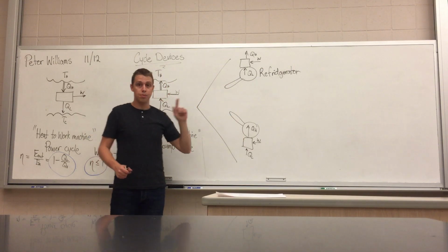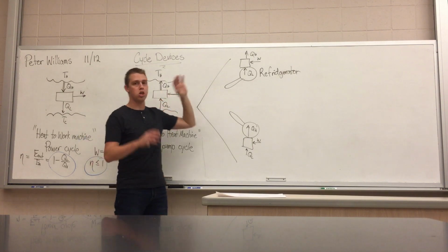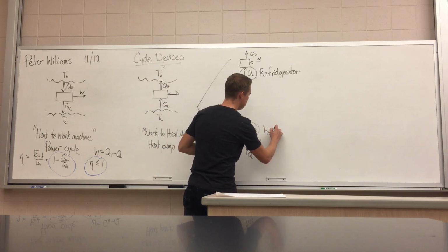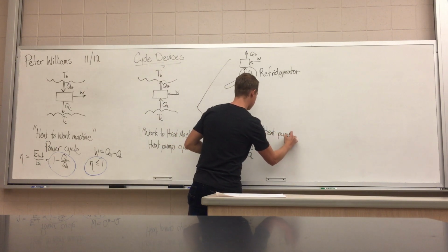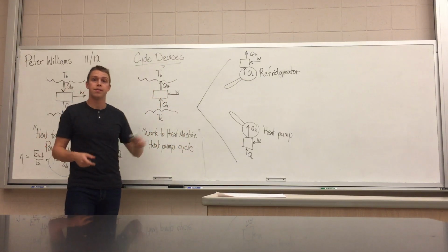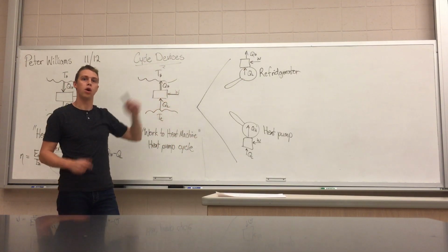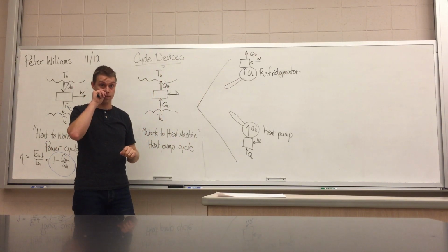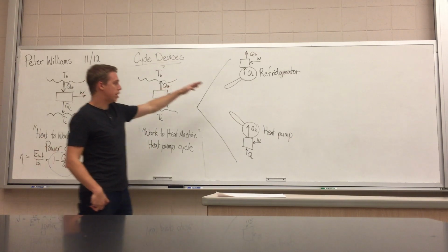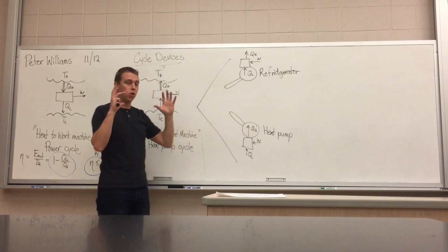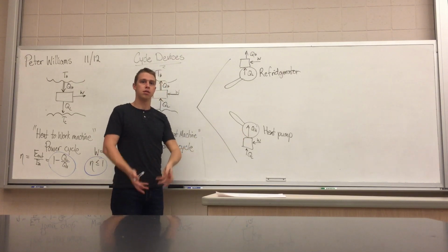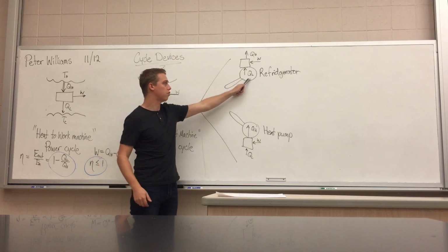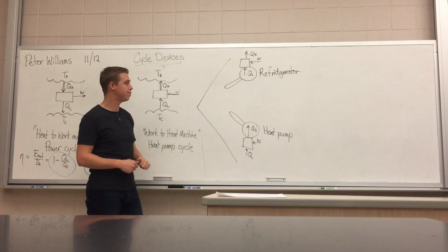So this is something that people get confused by, thinking that there's some huge difference between a refrigerator and down here, where the word for it is a heat pump. Okay? There's not. They are the same machine. I want you to understand that. This machine and this machine are the same. Okay? The only difference between them is where our focus is. Are we focused on how much heat we can pump out or how much heat we can suck in to our machine, away from the cold area or into the hot area.